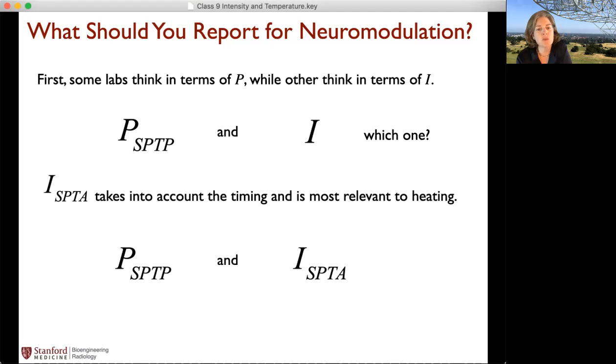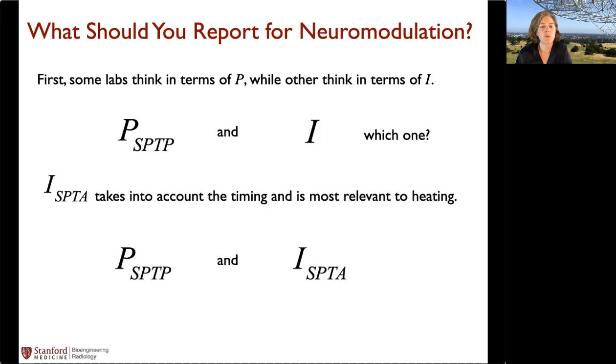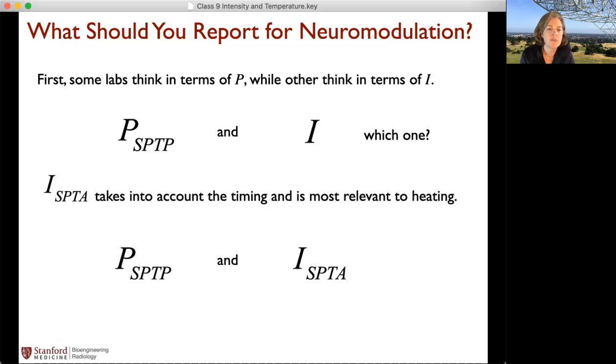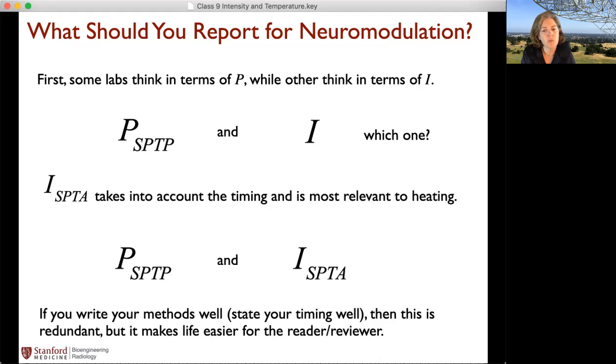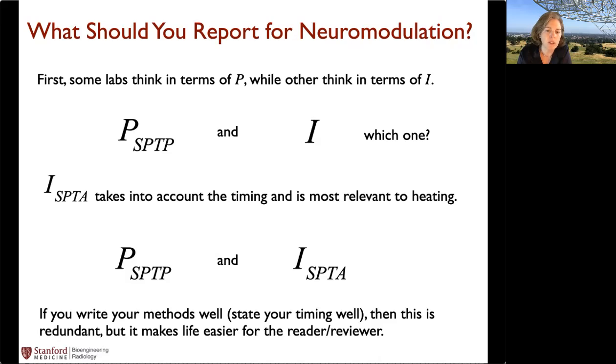So my feeling is that we probably should report both. And the argument against that is that, well, they're related to each other. All you have to do is figure out what the temporal peak is, then you can square it, divide by the appropriate constants, and figure out what your intensity is and account for that. But it just makes it a lot easier for the reader and the reviewer if they have one parameter that's reporting something related to mechanical effects and one that's related to the heating possibility. And while they are sort of redundant, if you explain the timing of your ultrasound pulses very well, sometimes it's a little unclear what the timing is.